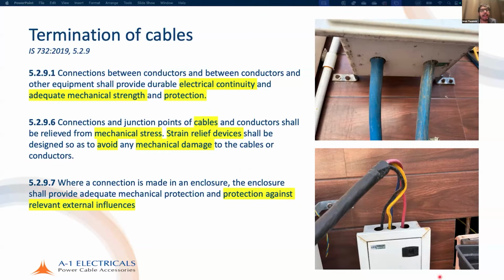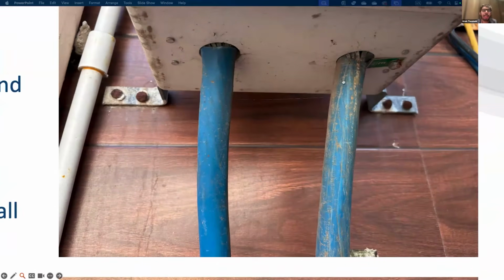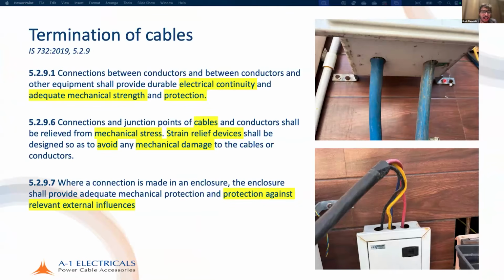Where a connection is made in an enclosure, the enclosure shall provide adequate mechanical protection and protection against the relevant external influence. So you'll see this word coming up a lot: external influences. If I zoom into the image here, you can see this is a very, very standard arrangement in India. We have an armored cable entering a piece of equipment. Firstly, there is ingress of water, dust, etc., and this has not been sealed. The armor is also just lying there. So we do not have adequate mechanical strength, no strain relief, and no protection against external influences.